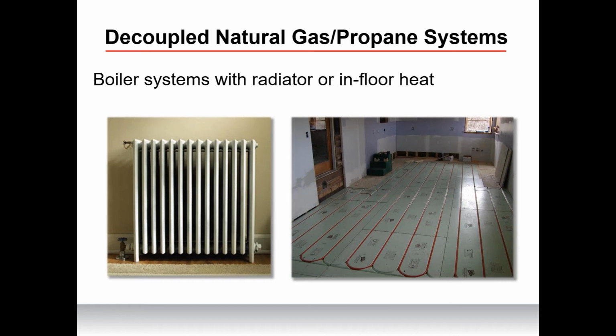The application would depend on whether the heat pump system is sized for cooling or primary heating. By combining two systems like this, you get the high efficiencies of zoning of the air source heat pump, along with the comfort and high heating capacities of radiant or in-floor boiler heat. You can also control how and when each system will turn on or off.